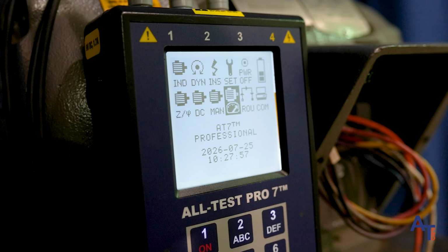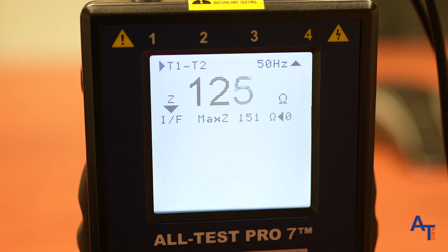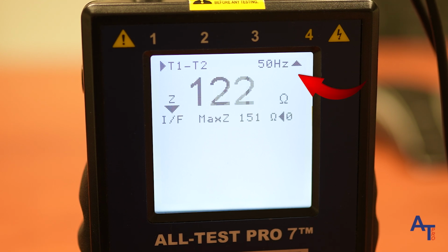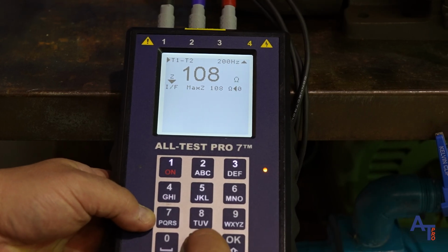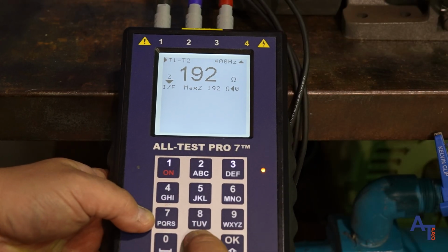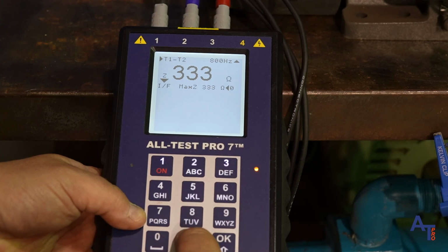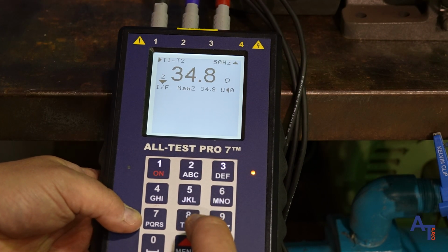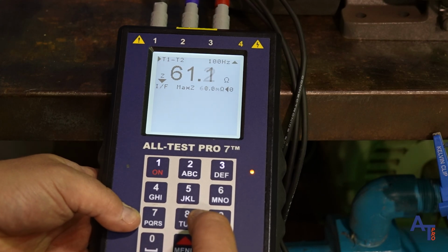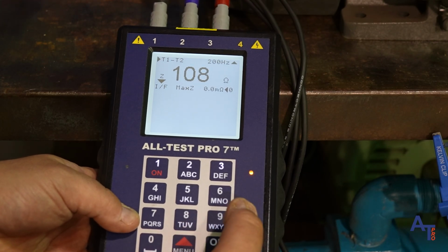The real-time test offers a unique advantage. The real-time test offers manual control and real-time visibility at a single user-selectable frequency. This flexibility allows technicians to cycle through 6 available frequency ranges to uncover hidden issues and confirm the motor's true condition. This is especially true when a motor is found to be good at only one of the 5 fully scanned frequency ranges.